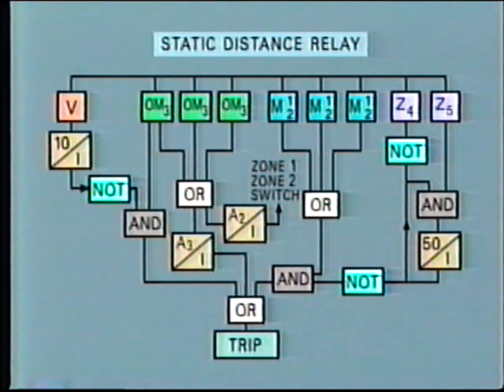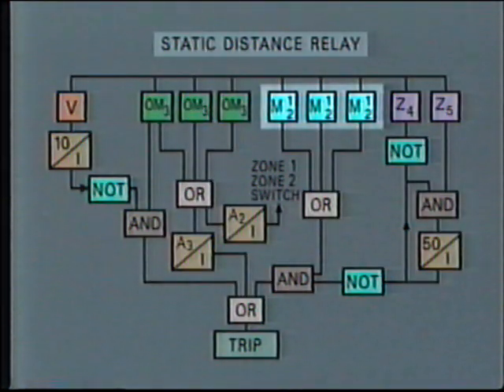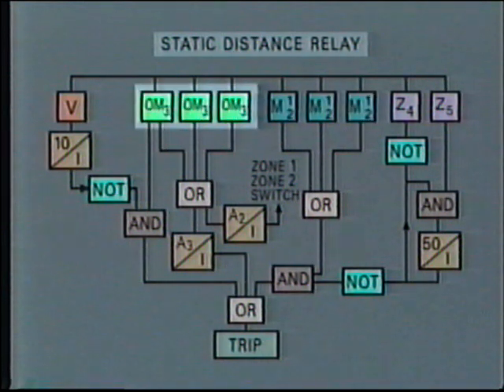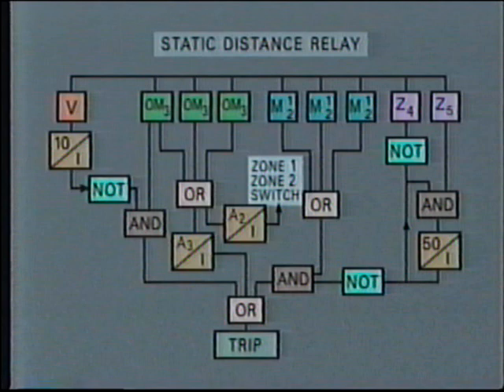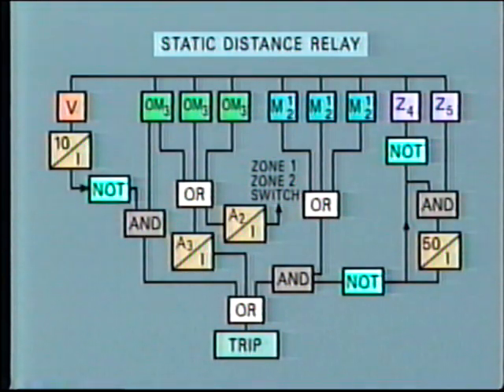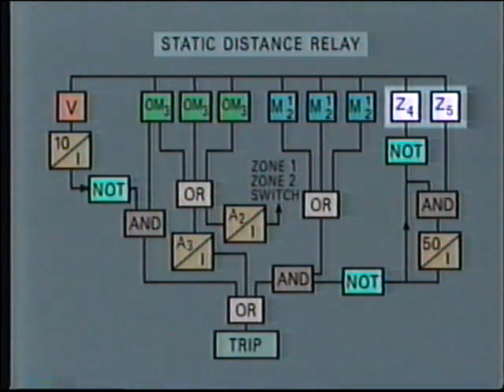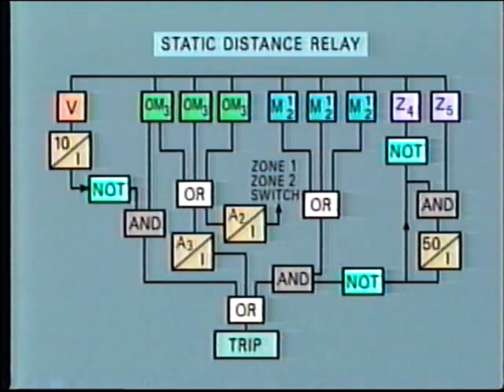Here is a block diagram of one type of static distance relay. This includes a two-zone Mho relay for each phase, shown here. We also have for each phase an offset Mho relay. This acts as a backup for zone 3 and also as a starting switch for the zone 1 and 2 relays. You will remember the significance and characteristics of these relays from our earlier tapes. Also installed are two impedance units. These are really auxiliary relays that block tripping in the case of severe power swings. This diagram, like all of the others, is included in your workbook, so you'll have more time to study details.